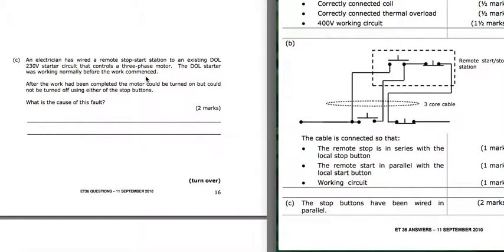This electrician has put this remote in, and after we've looked at the motor, turned the motor on, we can start it, but we can't stop it. So what that suggests is that these stop buttons have been put in parallel rather than series. You can see that the stop buttons have been wired in parallel, and so just breaking the stop buttons won't break the supply to the motor.